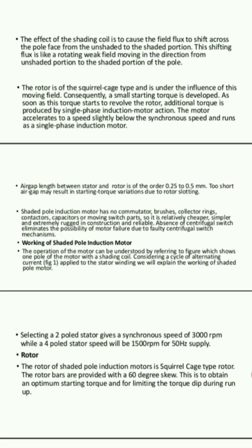The shaded pole induction motor has no commutator, brushes, collector rings, contactors, capacitors, or moving switch parts, so it is relatively cheaper, simpler, and extremely rugged in construction and reliable. Absence of a centrifugal switch eliminates the possibility of motor failure due to a faulty centrifugal switch mechanism.